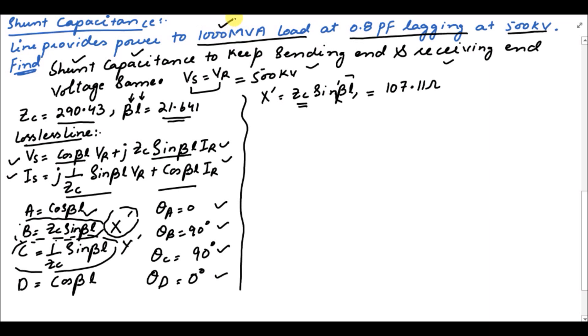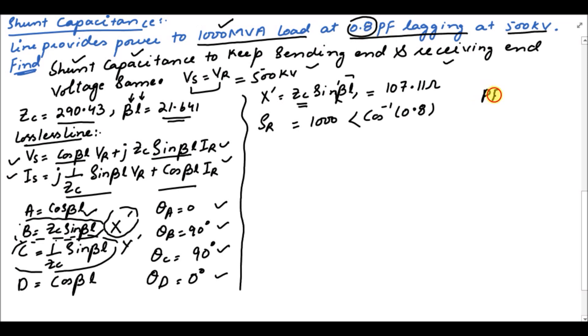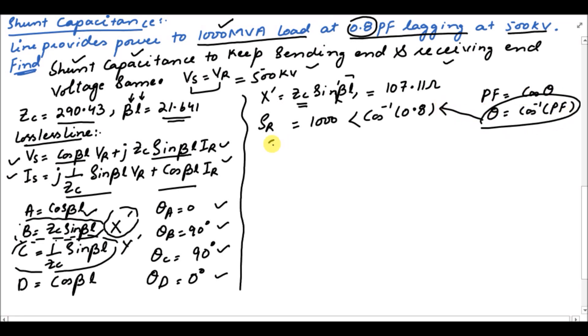In the question it is given that the load to be provided power by the transmission line is 1000 MVA at 0.8 power factor lagging. So we can calculate the apparent power at the receiving end: SR is equal to 1000 at angle cos⁻¹(0.8), since the power factor is 0.8 so theta equals cos⁻¹(0.8). Therefore SR is equal to 800 + 600j MVA.